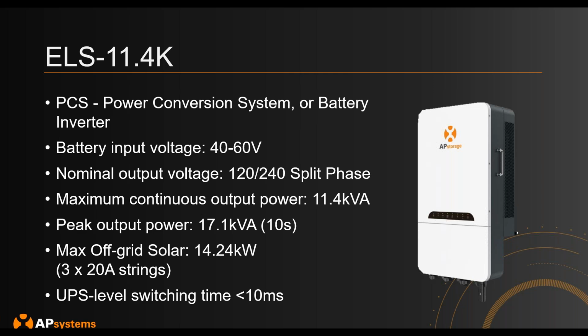It kicks in less than 10 milliseconds when you lose power. One other thing to note is that the 11.4K also disconnects itself from the utility during a grid outage, so it does not provide any backfeeding to the system.